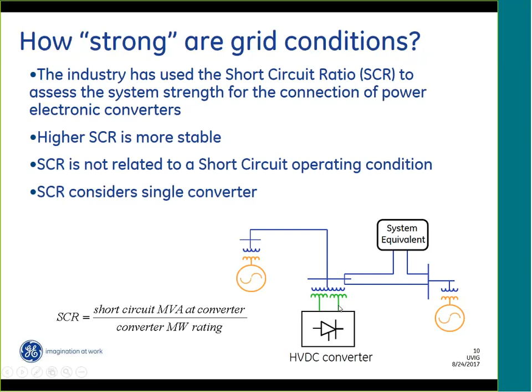This is a typical setup. I have 3 wind plants connected to a transmission network. And let's say I want to understand if there is a risk of the type of interactions or voltage stability issues that we talked about before. Well, one of the first challenges is that here we don't have a single converter, we have many. In general, the interaction with manufacturers, which I'm going to elaborate on later, allows you to consider a single plant as a single entity. But still, you very often have more than one plant. So the use of the short circuit ratio is kind of complicated here because we cannot exactly do the same thing. If we try to apply the short circuit ratio to each of the plants individually, calculating short circuit for this plant and ignoring the other plants, that's going to lead to optimistic results.